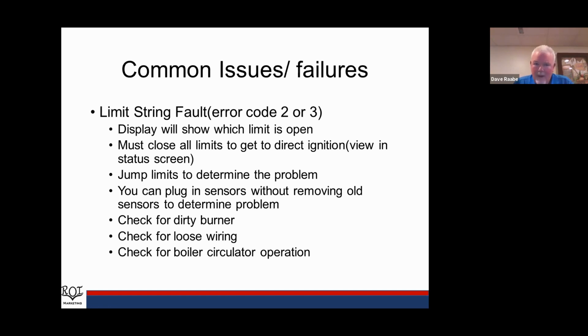The other thing on an error code 2 or 3 or a failure to ignite, I would check for a dirty burner. If we get our air pressure switch to say that three times quickly, that doesn't make, but my blower is running, there's a chance I could have a plugged up burner. Our burners basically look like a soup can with a bunch of little holes around. And if we're pulling in dirty air, those holes can get plugged up, and then we can't get that gas air mixture to go out through them properly. So I would recommend checking for a dirty burner. And if we see that, you can take compressed air and just blow that burner out, blow whatever's in there out.